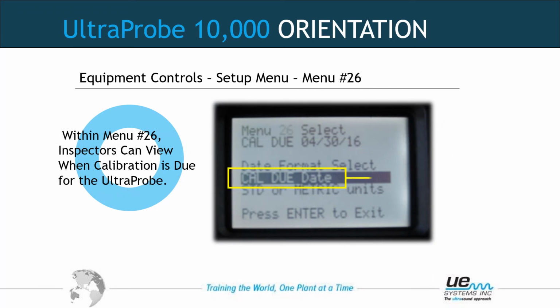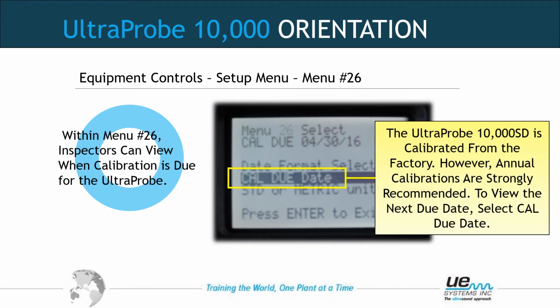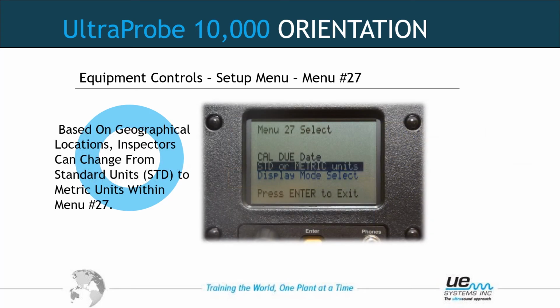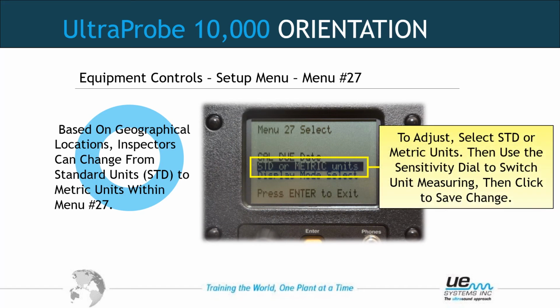Menu number 26 is calibration due date. This is when the unit is due in for calibration. This would be 12 to 13 months from when it was last calibrated. Not when it was calibrated, but when it is due for calibration is shown here. Standard or metric units: it's defaulted to standard units. You can change that to metric, but that is for the input data such as pipe size, orifice size, things like that. It does not affect the dB or the frequency.